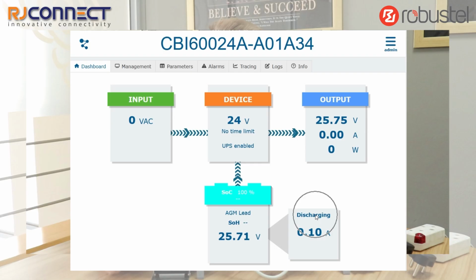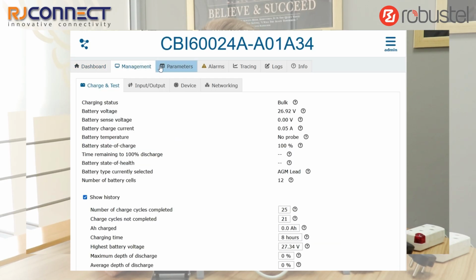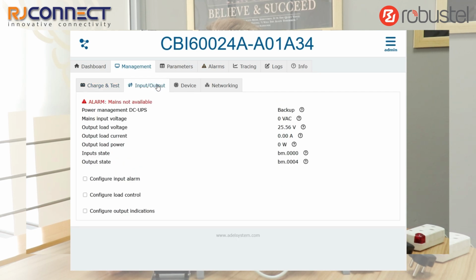While the system is running, I will review the battery diagnostics. The RJU monitors battery condition, and can report issues such as low battery voltage, battery disconnection, incorrect polarity, poor internal battery condition, or other fault states. These diagnostics help identify battery problems before they cause a loss of backup capability.